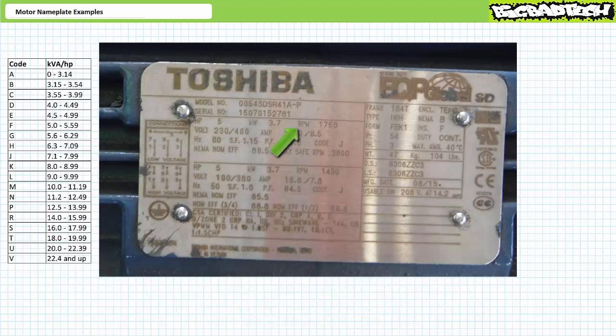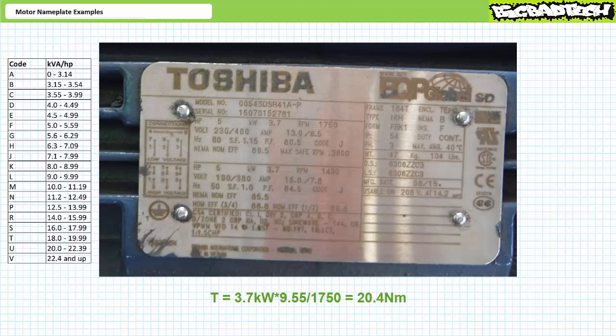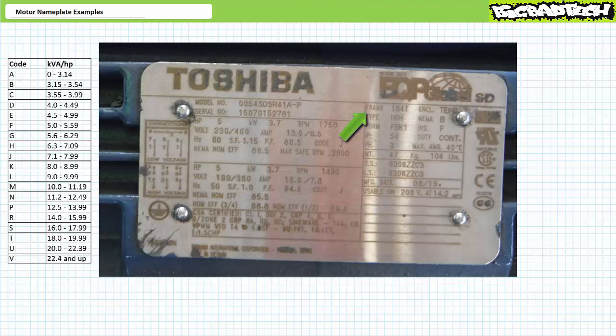This motor has a rated speed of 1750 RPM. Knowing mechanical power and speed, we can back-calculate torque by substituting into the algebraic manipulation of the mechanical power formula, which demonstrates this motor must be producing 20.4 Newton meters of torque at the rated condition. This motor has a NEMA 184T frame and a TEFC enclosure, which stands for totally enclosed fan cooled. This type prevents the free exchange of air between inside and outside the frame, but doesn't make it completely airtight. A fan on the non-drive end keeps the motor cool during operation.